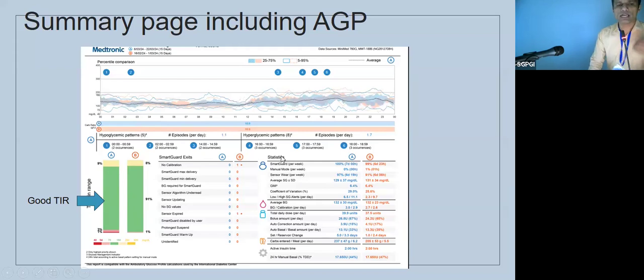Now, what are the other components that you will see? These bars represent the time in range, above range, and below range. In above and below, you have stage 1 and stage 2 hyperglycemia and hypoglycemia both. This particular column is giving SmartGuard exits. That is the number of times the pump exited from the automatic mode into manual mode as a backup. This has happened once because the sensor was expired, and once here because there was no calibration done.